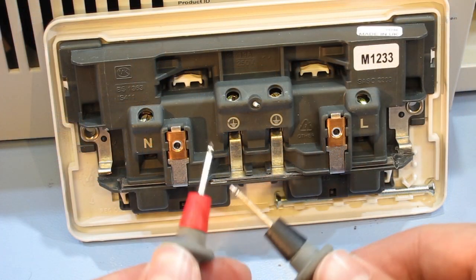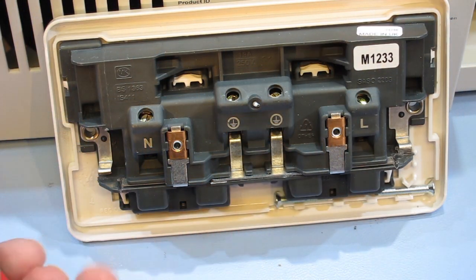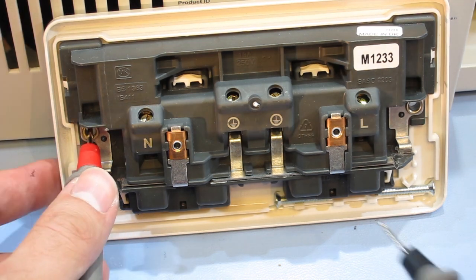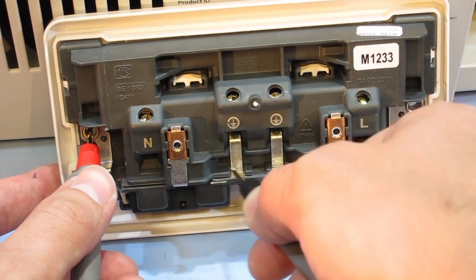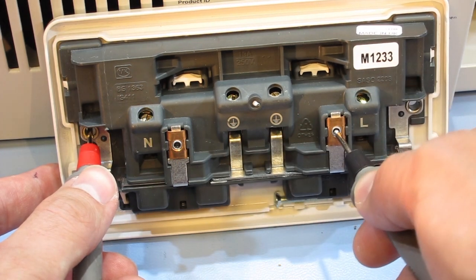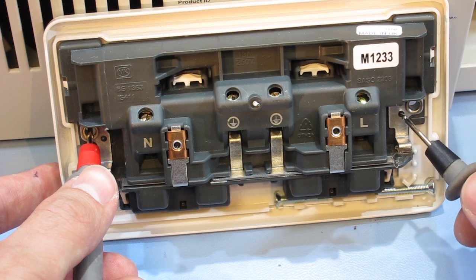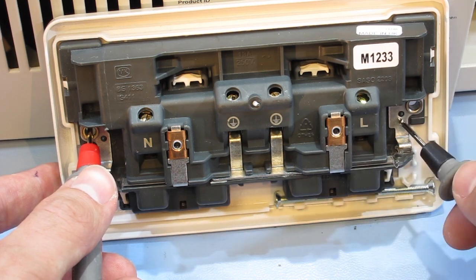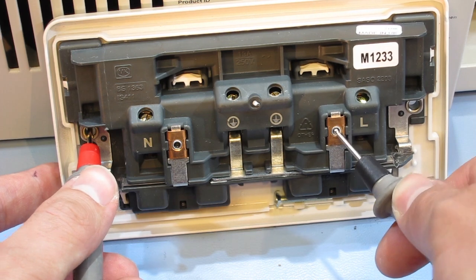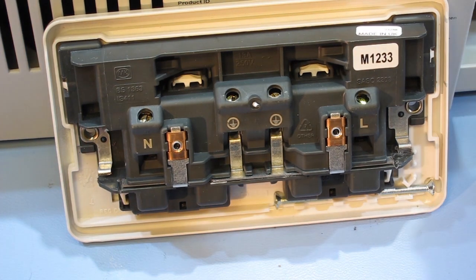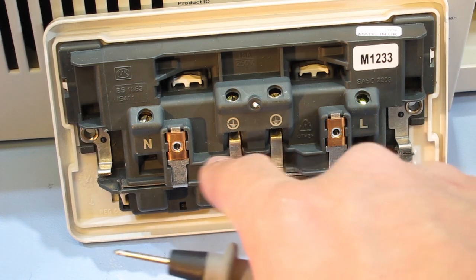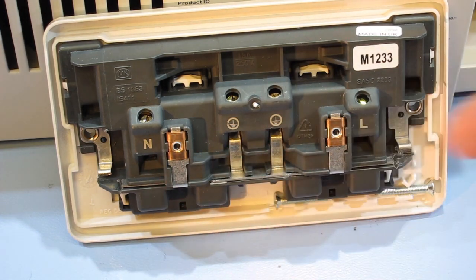Okay, so we've got the meter on continuity, and if I just hook in the probe onto the front here and we touch here, we can see we've got no continuity whatsoever. And then if I just touch the front panel the other side, we have a good low connection. So the mounting screws that I use to mount the socket to the front cover should provide adequate earthing of the actual plug itself, but the earth terminals of the socket I can then loop out onto the banana jack on the top cover of the transformer.